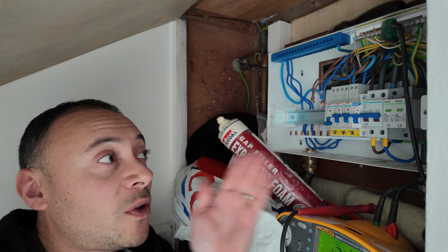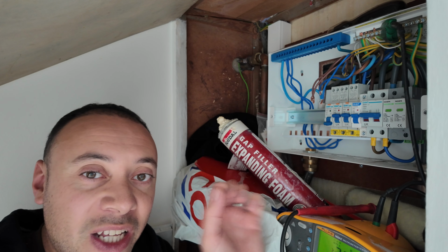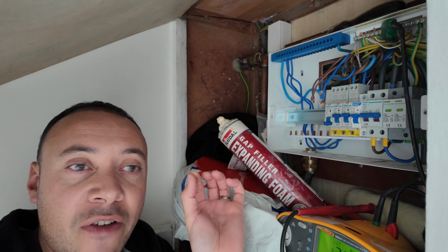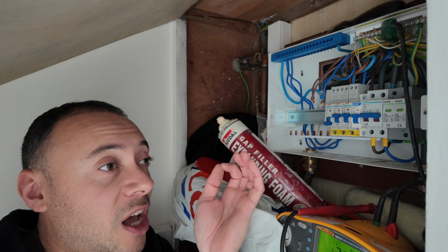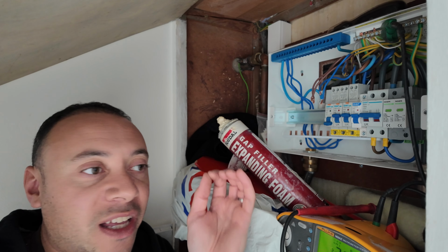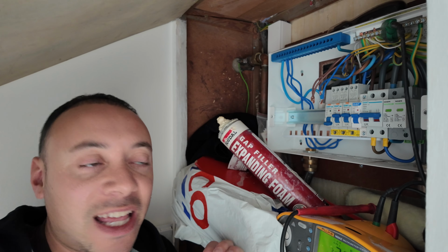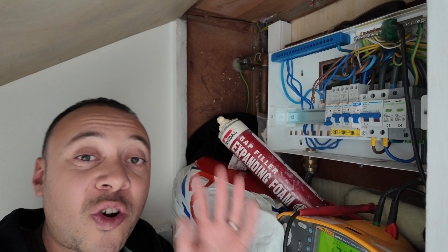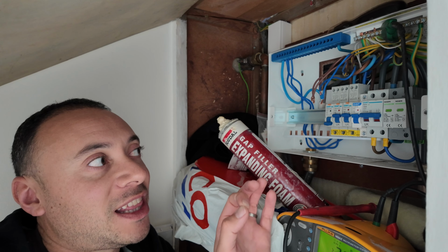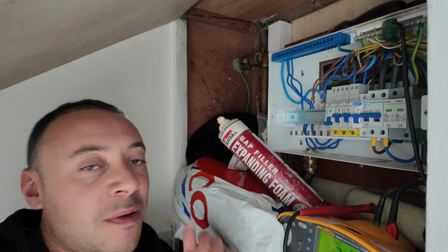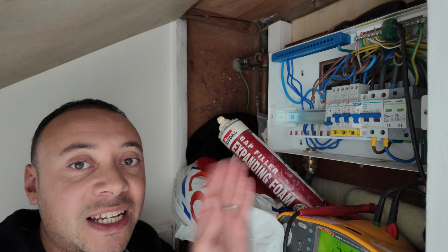Right now, if there was a fault that was coming and going, I'd normally expect the reading not to be over 200 megohms, which basically states that it's like infinite. I'd expect the reading to be down. I might get something like 10 megohms, indicating that it's okay. It's an okay reading, but it's not a great reading. But in this scenario, I'm getting over 200 megs, so that indicates that there is nothing wrong here. Never say never, but that's the way it's indicating at the moment.